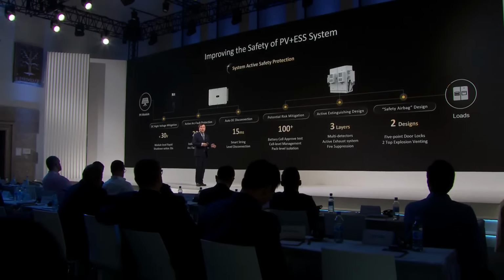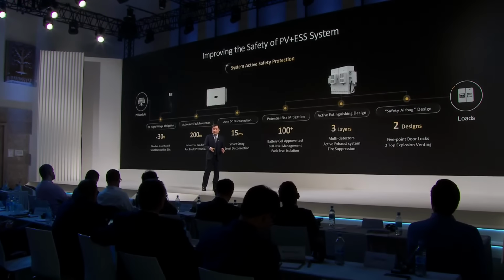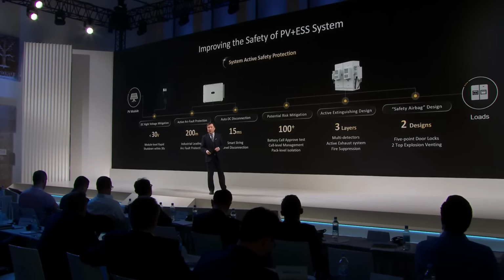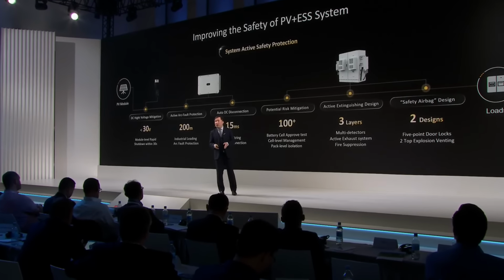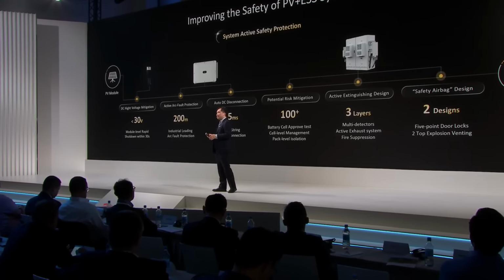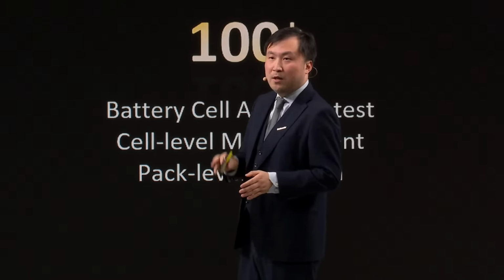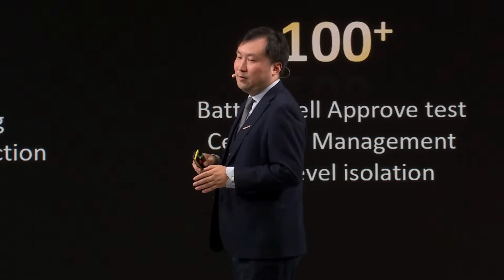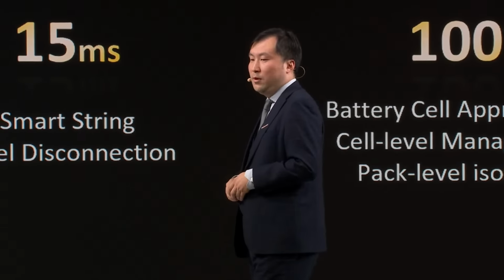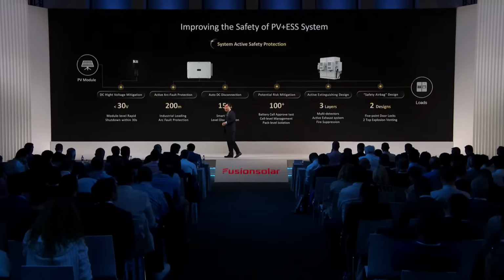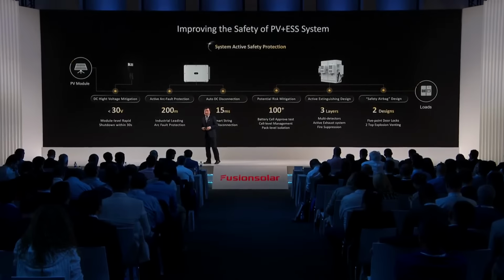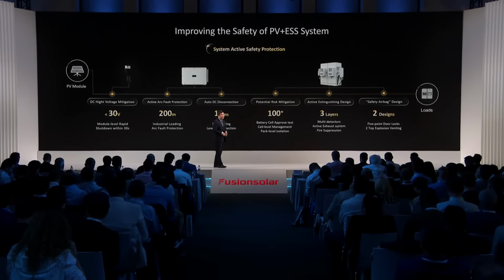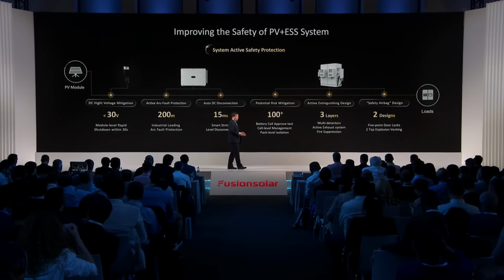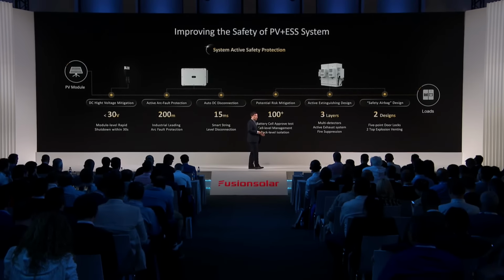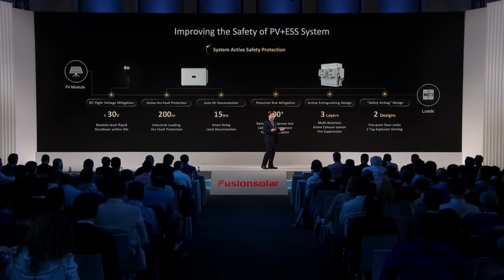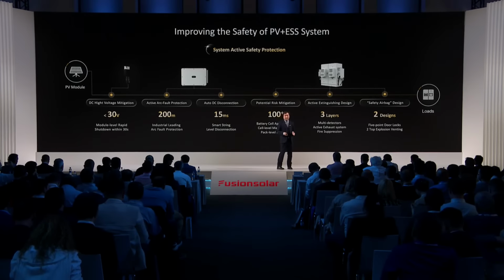But despite every single protection method, how to cooperate RSD together with AFCI is always a challenge, because arc protection requires precise acquisition of high-frequency signals on the DC cable. At the same time, the optimizer causes some noise or uncertain signals on the DC cable, which causes interference. We carried out a systematic design in both optimizer and inverter from the beginning, and with the intelligent frequency selection algorithm, Huawei can avoid any misjudgment caused by this interference. So the RSD and AFCI can work together perfectly.